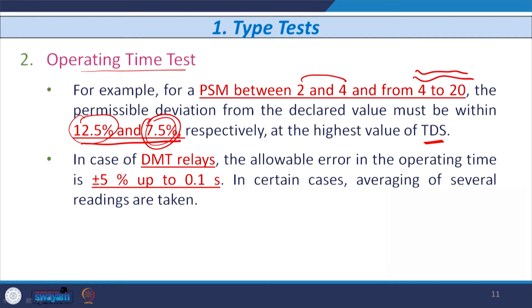If I consider the definite minimum time delay relays, the allowable error in the operating time is plus or minus 5%, say up to 0.1 second. In certain cases you can average it by considering a different number of readings. That is also another method, but again, for each and every value of PSM or multiple of pickup current, you have some allowable value of operating time, and it should not go beyond that range.